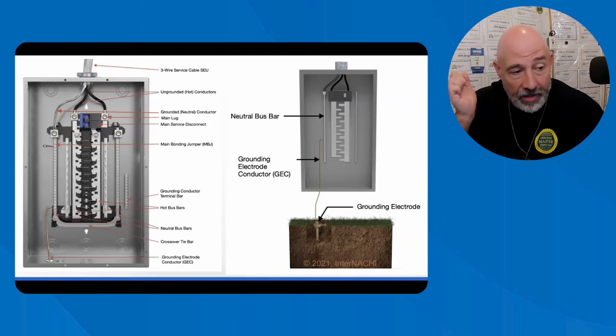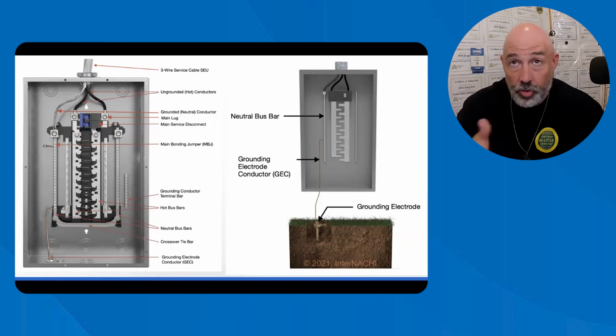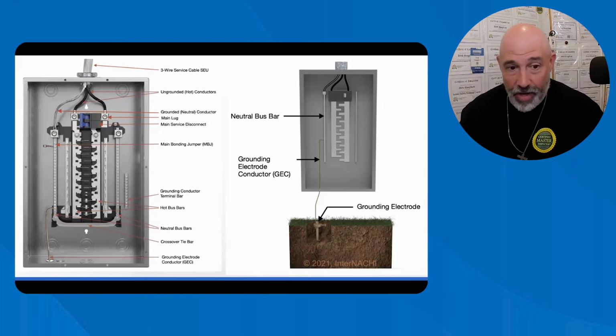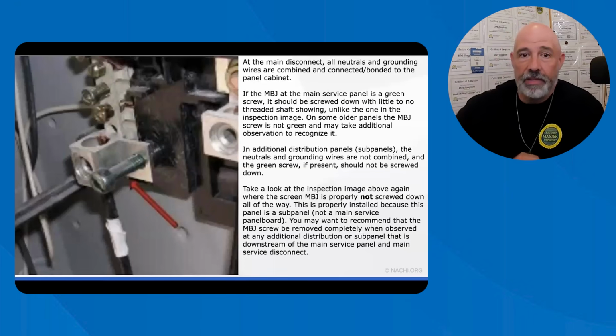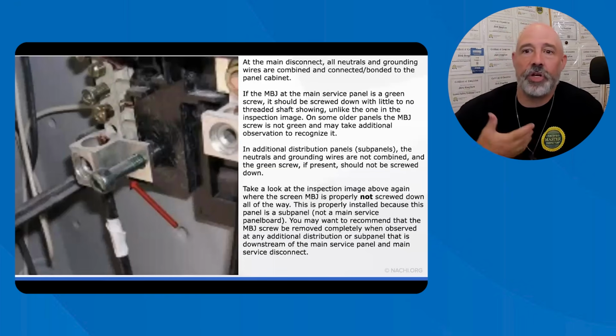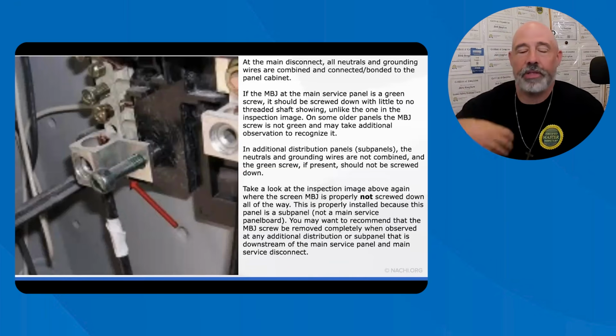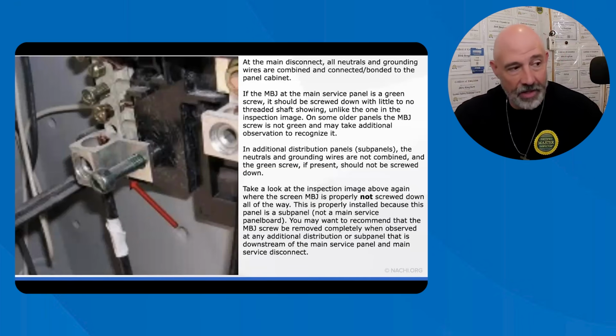And it also brings electricity back to the transformer if it was very high. A simple rule is bond once and only once at the main disconnect. So just marry them together right there. At the main disconnect, the neutral and grounding conductors are bonded together and connected in the panel. I feel like I want this drilled into your head. They get married at the main and divorced everywhere else.